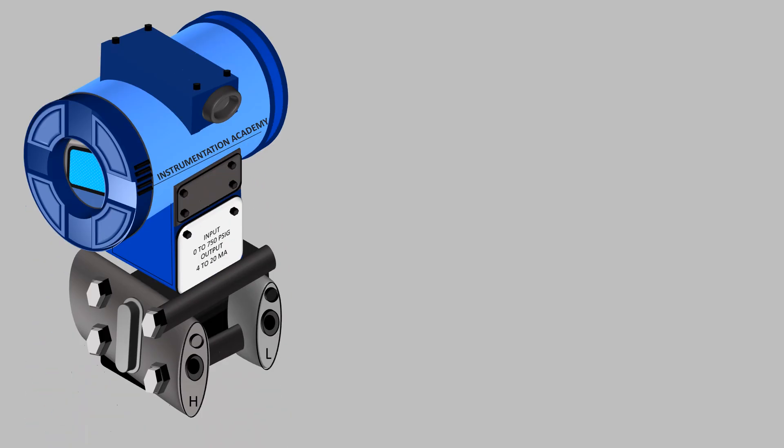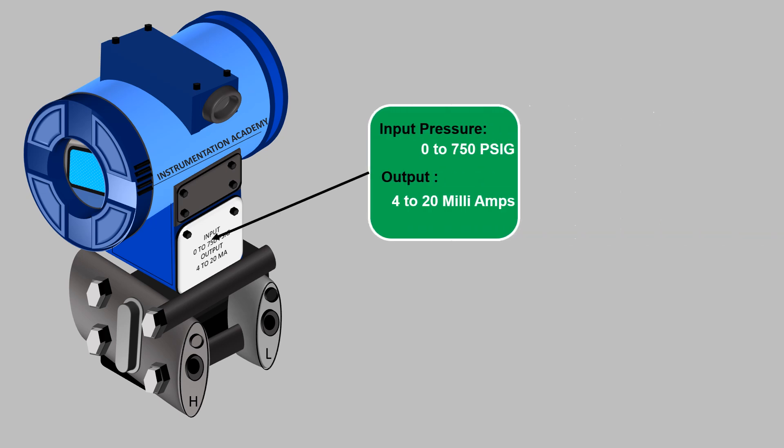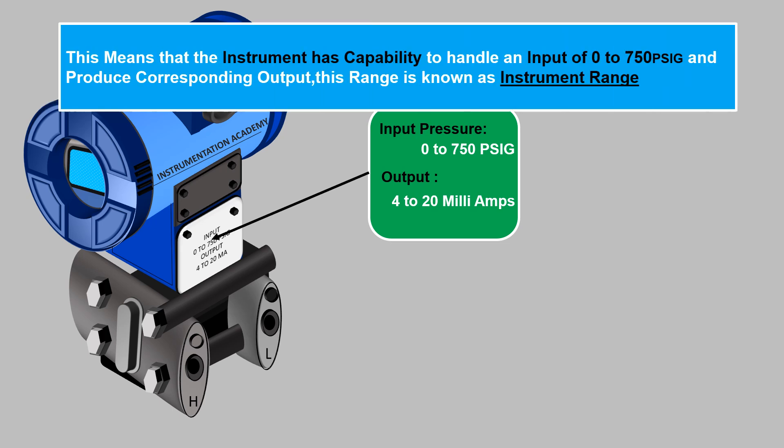Consider that the nameplate of a pressure transmitter shows an input pressure range from 0 to 750 psig and an output of 4 to 20 milliamps. This means that the instrument has capability to handle an input of 0 to 750 psig and produce corresponding output. This range is known as instrument range.